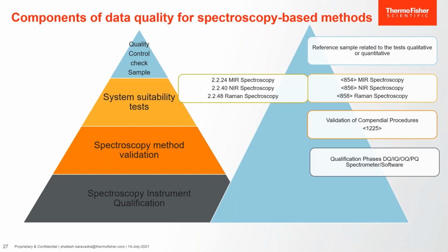There are also components of software validation, because most of the analytical instruments will be running on firmware. So there is a guideline on checking the firmware during the instrument qualification stage, also making sure that the software through which the operations are made on the instrument is also validated.